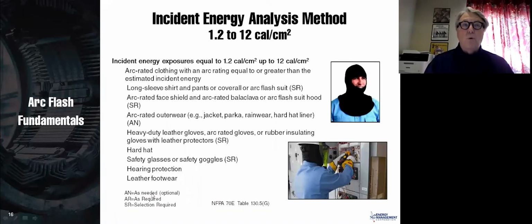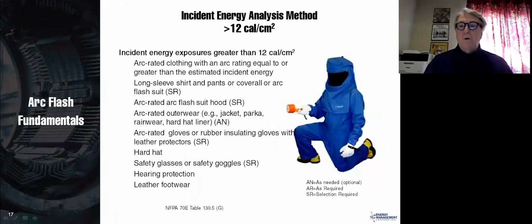If it is from 1.2 to 12 calories, you will need to wear shirt and pants or coveralls rated for whatever calories of equipment you are working on, and then your typical safety equipment. If it's over 12 calories, then you must wear a full arc flash or beekeeper or Buzz Lightyear type suit, as you can see there.